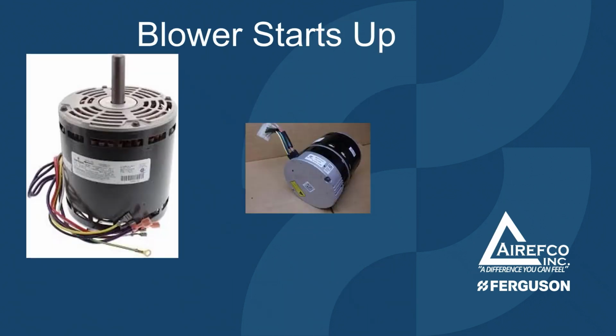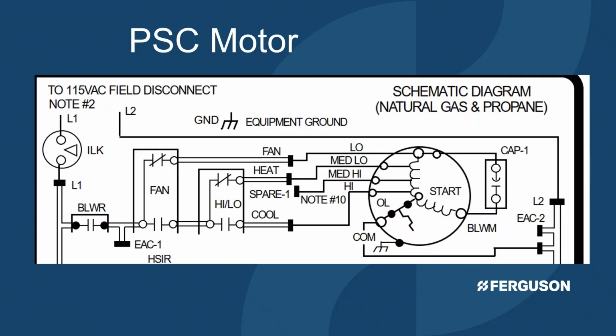After the flame has been confirmed, and after a period of time, the blower motor will start up. Again, as with the inducer motor, you have a standard PSC motor and also ECM motors for the blowers. On the PSC motor, you will have various connections for the various speeds of the motor. In this example, we have a common that is tied back to the line voltage, and then we have our cool tap that is connected to the high speed of the motor. Our medium high is not connected. Medium low is connected to the heat connection, and our continuous fan is connected to the low speed.